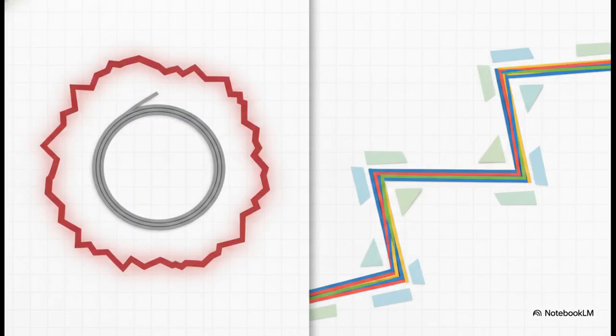Now consider the cable routing. You'd probably think they'd just coil the extra wire up nice and neat, right? Actually, no. The cabling has to be routed in a very careful zigzag configuration. If you coil a wire, you accidentally create an artificial induction loop, which is basically an electromagnet. By zigzagging the cables, engineers make sure they aren't accidentally inventing brand new interference that wouldn't even exist out in the field. Literally every single detail is controlled.